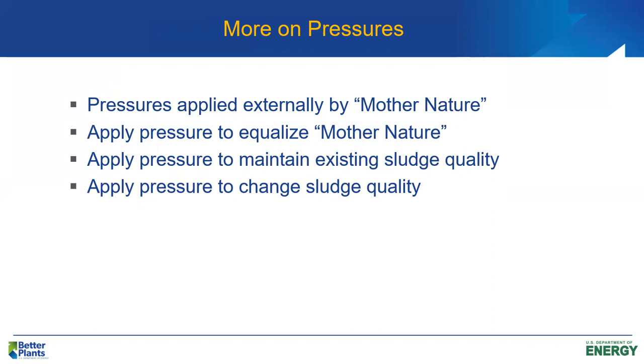I helped a large pure oxygen activated sludge plant whose pure oxygen production facility went out of operation for three weeks. What we did was take half of their Unox reactors out of service and operate at a very low sludge age in as few biological reactors as possible, trying to minimize our oxygen requirements and respond to the fact that we were having to pay a lot of money to truck in oxygen every day. We applied a pressure to try to keep decent sludge quality in a very difficult situation where we were not able to produce oxygen.